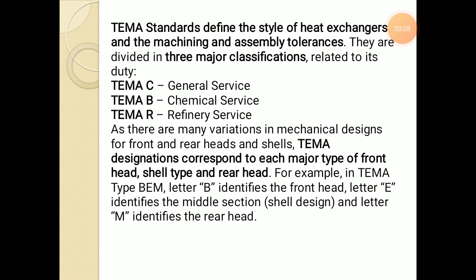As there are many variations in mechanical design for front and rear heads of the shell, TEMA designs correspond to each major type of front head, shell type, and rear head. For example, in TEMA type BEM, letter B identifies the front head, letter E identifies the middle section, that is the shell design, and letter M identifies the rear head. So these are the different removable bundle, internal split ring floating head types for AES and BES. As I mentioned, the first letter represents the front head, the middle represents the shell side, and the last letter represents the rear head.